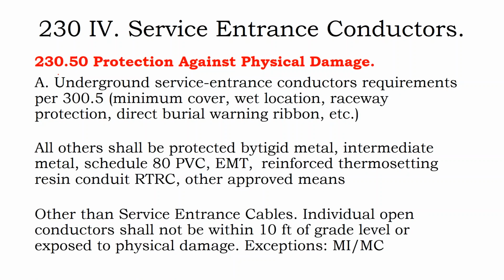Some requirements for physical damage. So there are different requirements. If you're doing an underground service entrance, you can do a direct burial requirement. But if it's not an underground service, you have to protect your service entrance conductors from damage. But that could include PVC conduit.